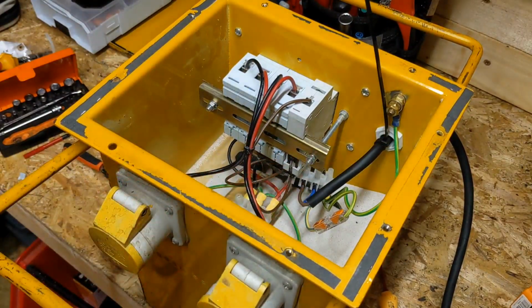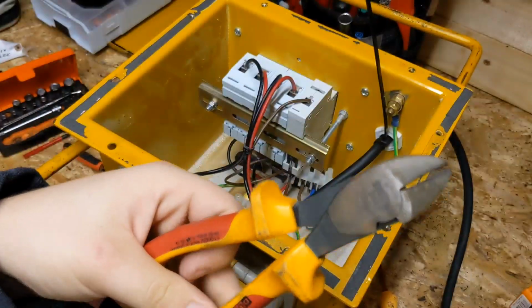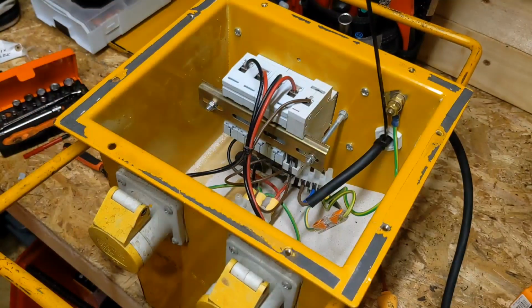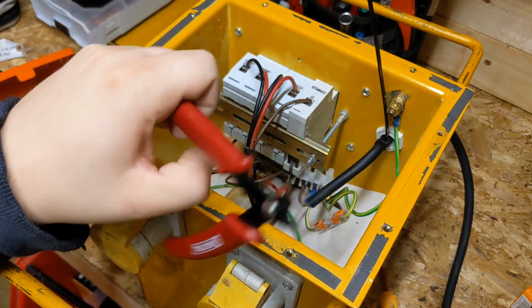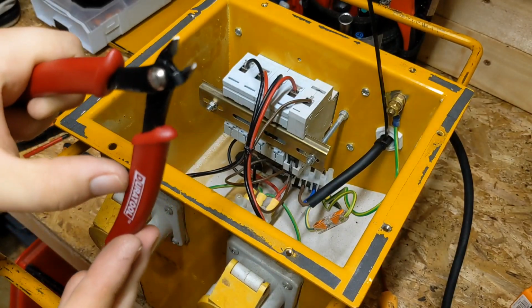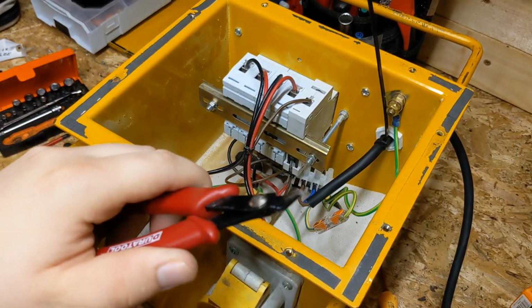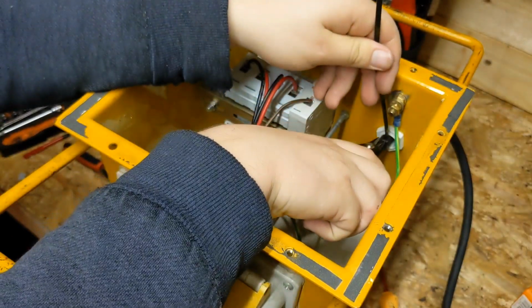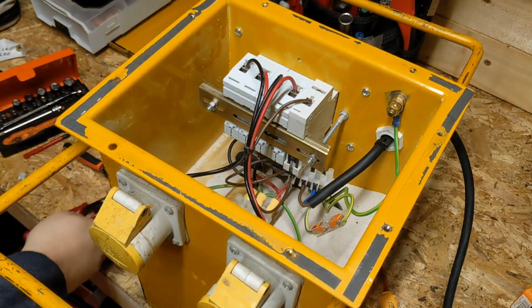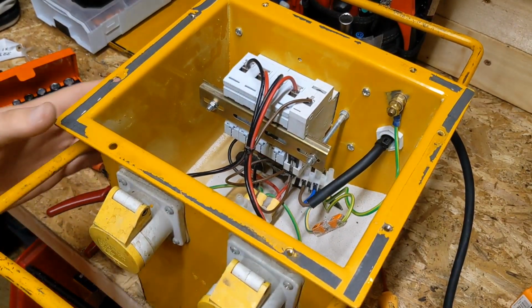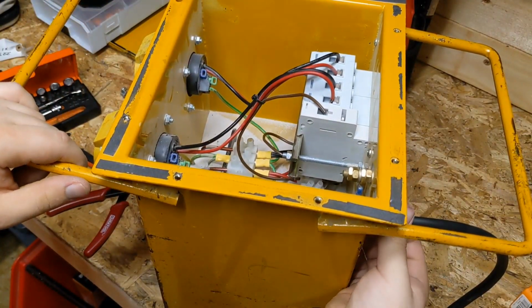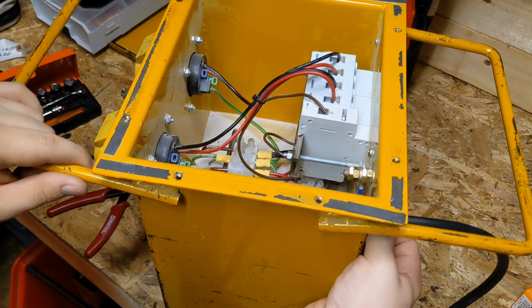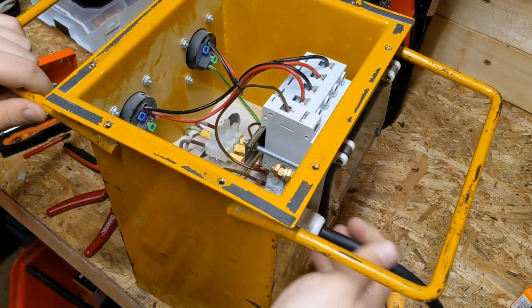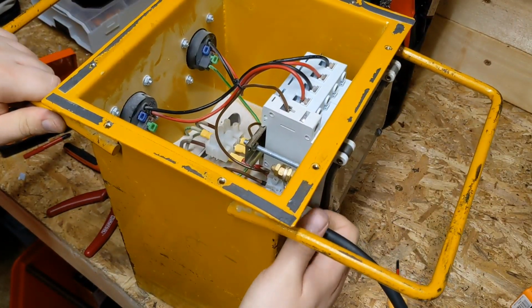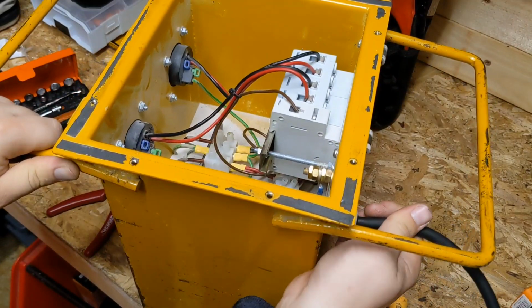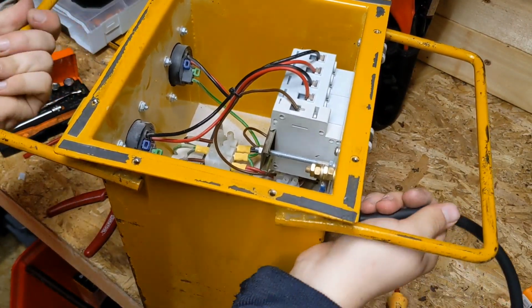Top tip when using cable ties: never cut them with side cutters like this, as they leave a sharp edge. You want electrical side cutters, or any cutters where the jaws slightly overlap, which leave a nice flush, non-sharp edge. So simply cut that off like so, turn it around, pull it up nice and tight. Now there's absolutely no way that cable's ever coming out under any normal operating condition - you'd have to really brutally force it out.